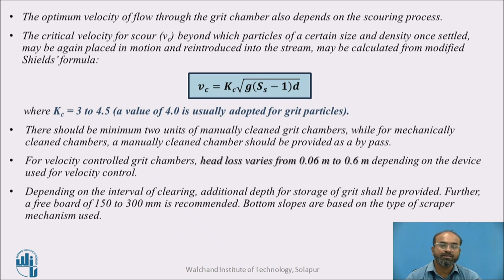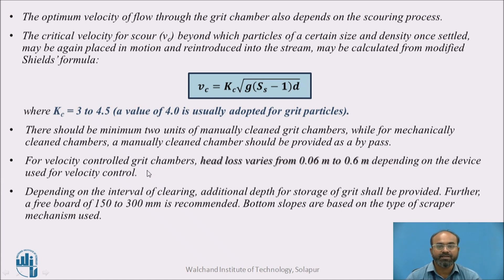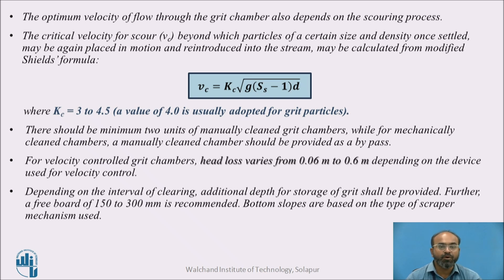For velocity-controlled grit chambers, the head loss generally varies between 0.06 metres to 0.6 metres depending on the device used for velocity control. Depending on the interval of clearing, additional depth for storage of grit shall also be provided. Further, an additional freeboard between 150 to 300 mm is recommended. Bottom slopes are based on the type of scraper provided for a typical grit chamber.